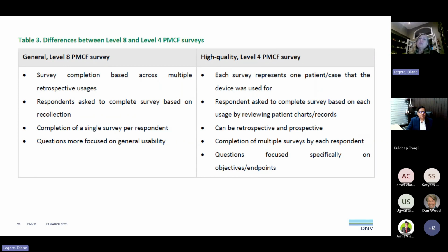So here again is where a lower class device has some wiggle room when we look at the totality of your evidence. You're going to show us your bench testing, your standards that you tested to, all preclinical. Supportive data can't be used in place of clinical data, but I'm going to consider it and weight it more than, say, a class 3 device that goes into a coronary artery. Then your post-market data, that is clinical data, and you're going to show me trending.